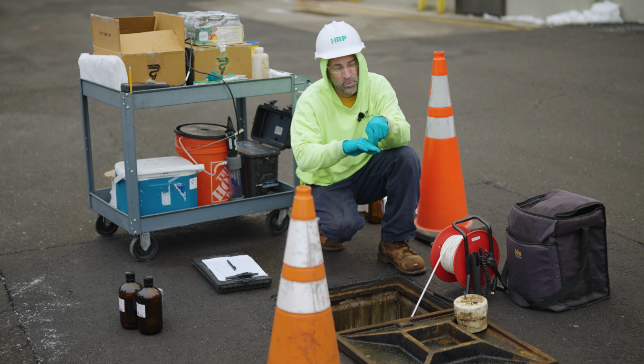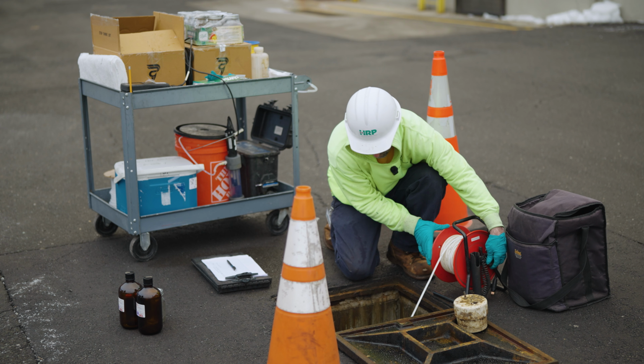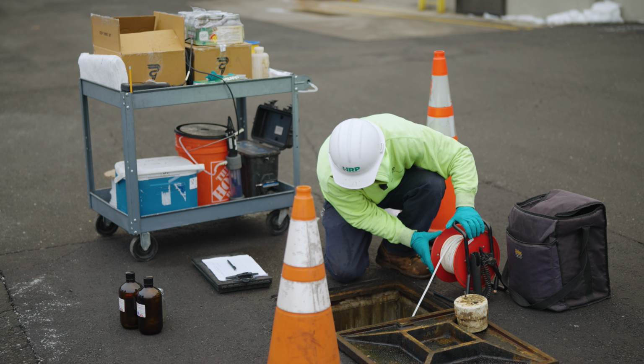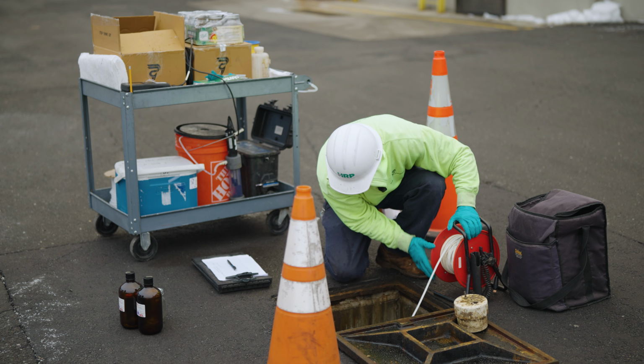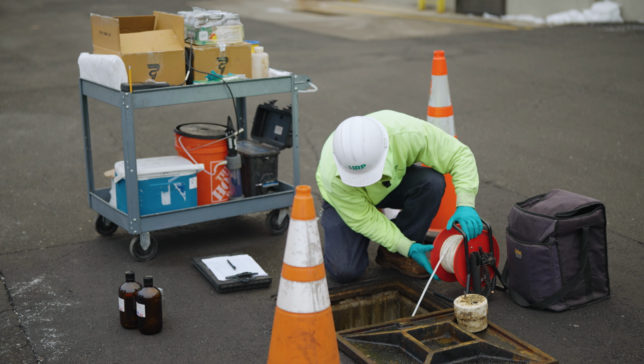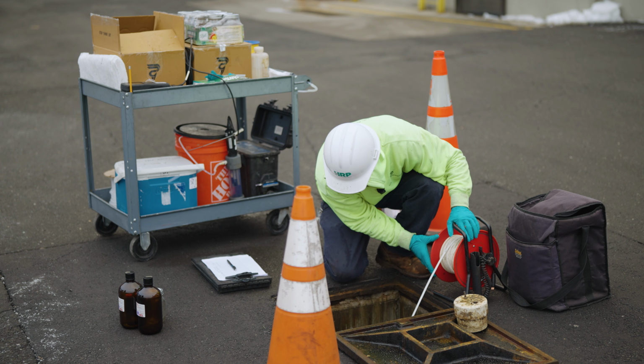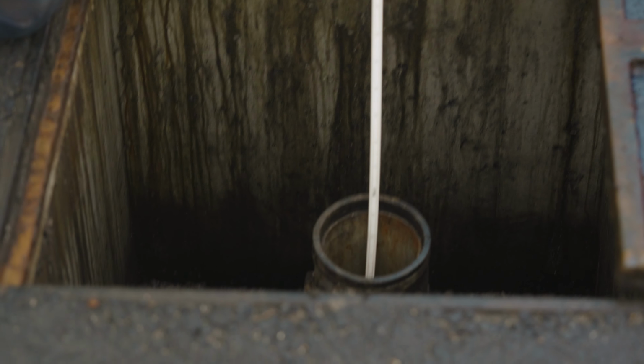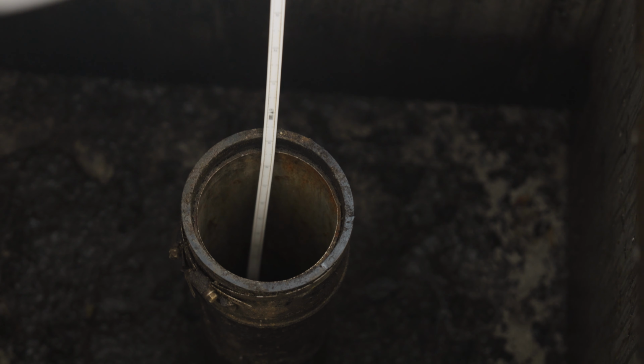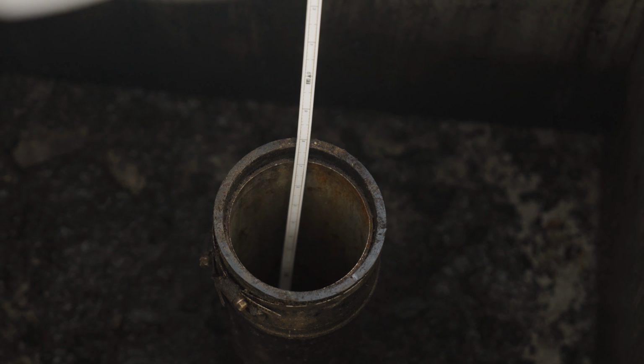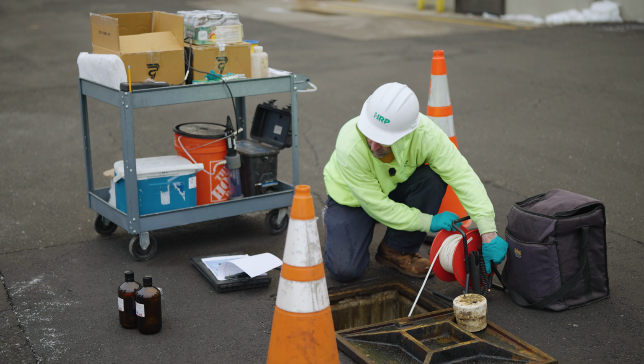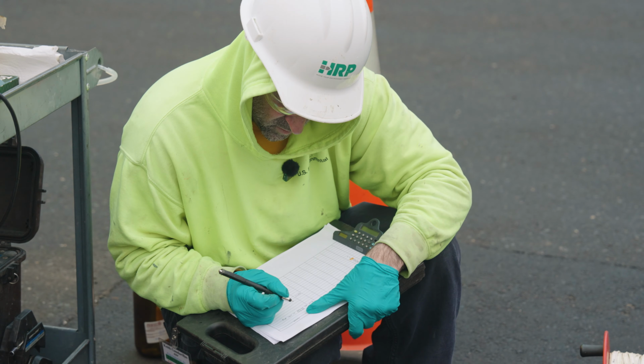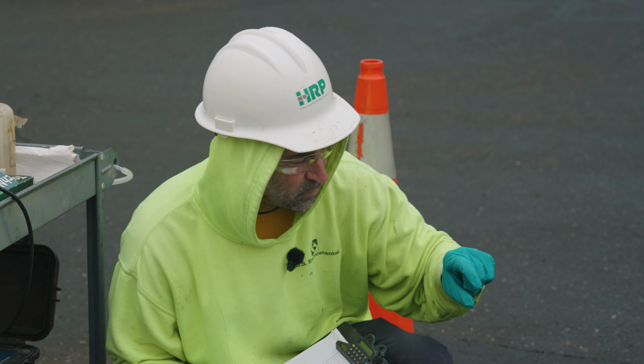Now we've got the level of the oil, we're going to need to get the level of the water. So we're going to stick our probe down further until we hear the intermittent. And then we're going to come back up until it gets solid, and that'll be the layer of water underneath the oil. And usually check it a couple times just to confirm. All right, so that's reading 5.69 to water. So we have 0.33 thickness of oil in this well.